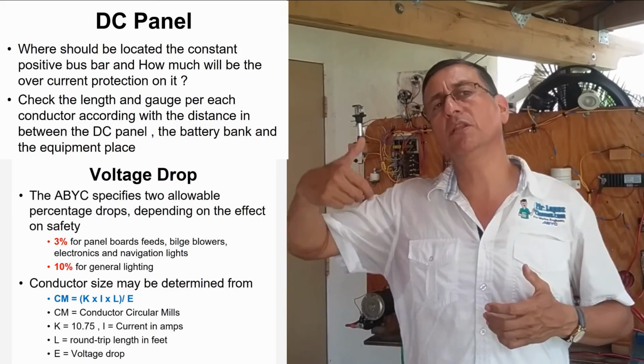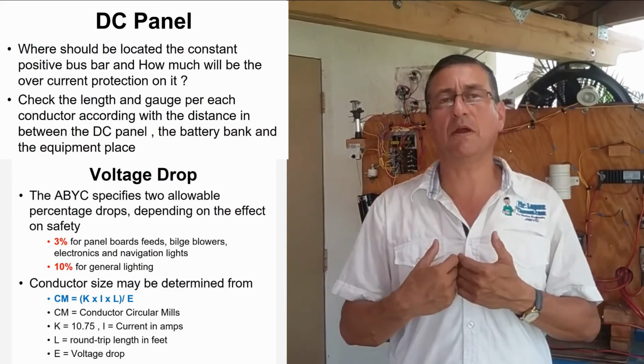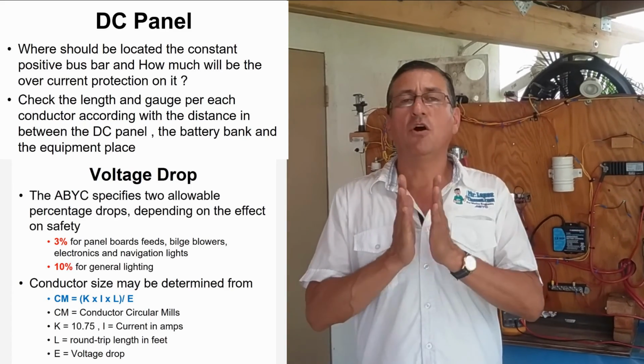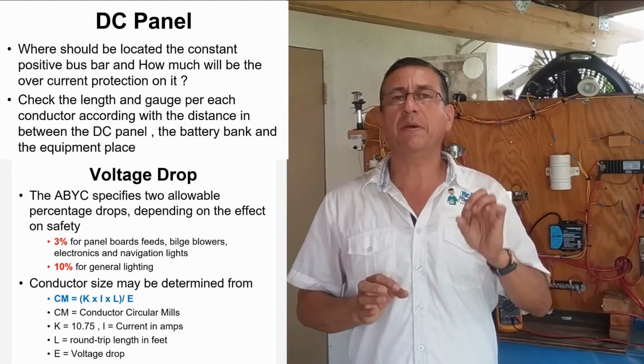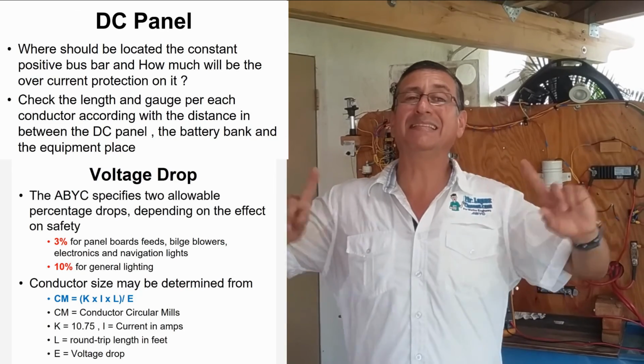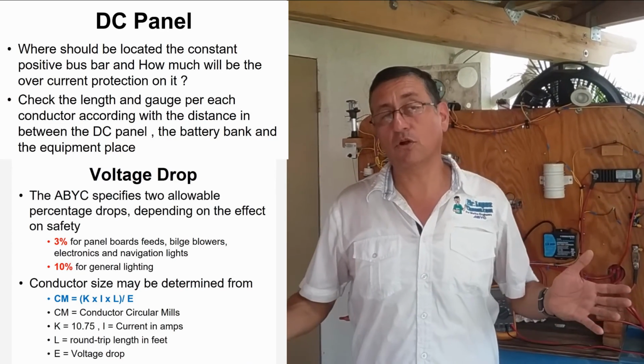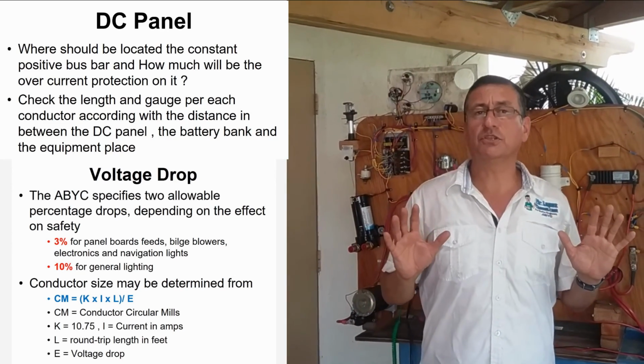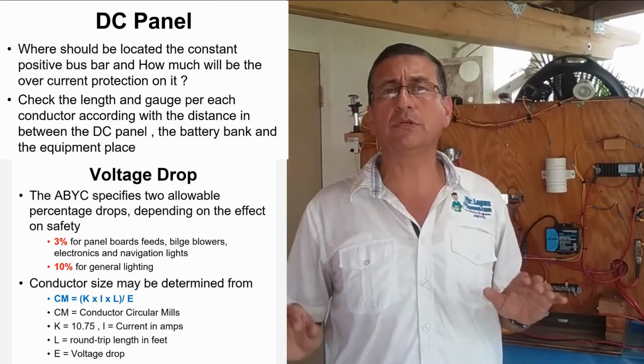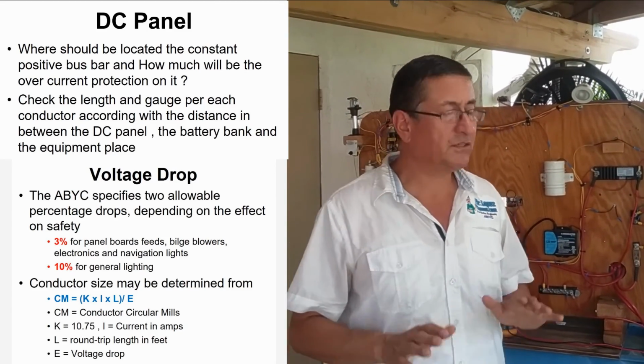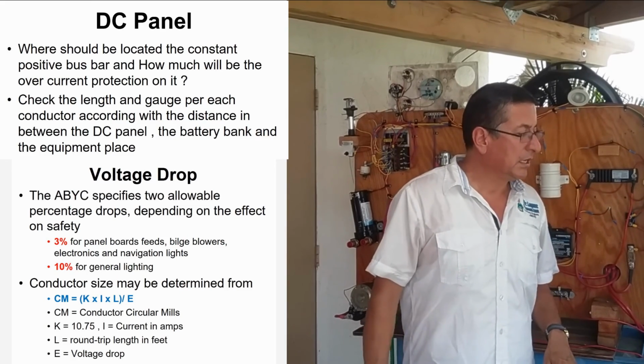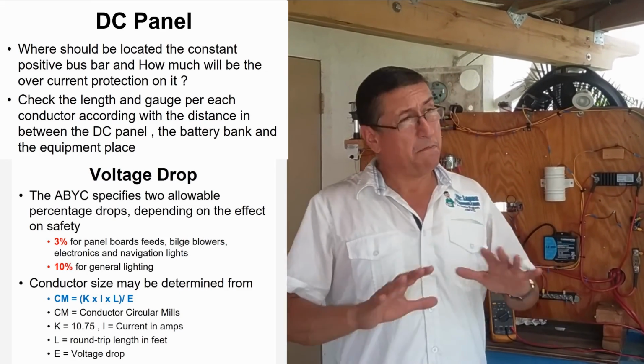Use the table from ABYC or use my formula. All of those gauges depend on the consumption in amps, the total length, and of course the voltage drop, which is mandatory: 3% for general purpose and 10% for lighting. This is the most important information.